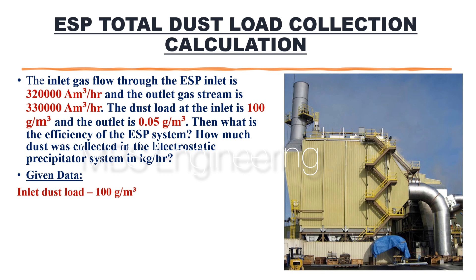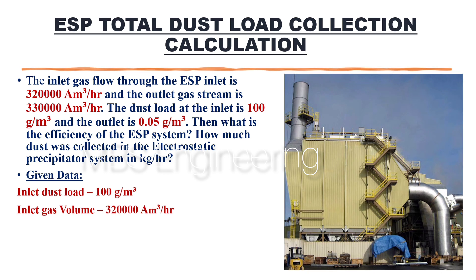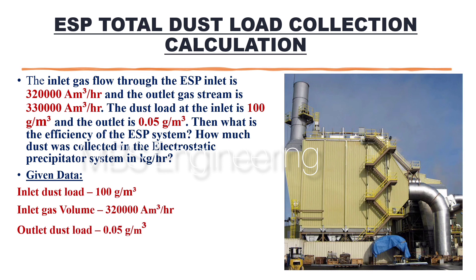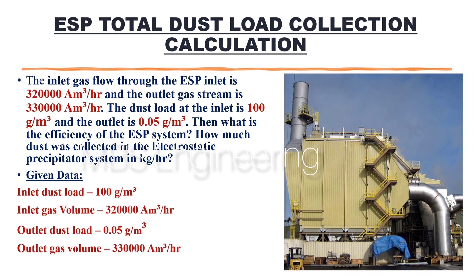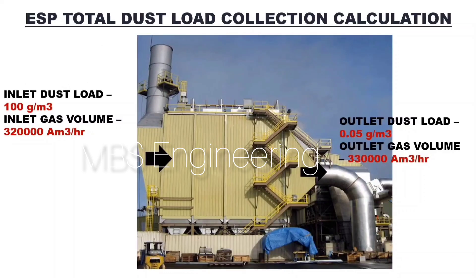Given data: As per the above scenario, the below parameters are given. The inlet dust load concentration is 100 grams per cubic meter. The inlet gas volume is 3,20,000 cubic meters per hour. The outlet dust load concentration is 0.05 grams per cubic meter. The outlet gas volume is 3,30,000 cubic meters per hour. Please refer to the below snaps to understand how to calculate the ESP total dust load collection in the given inlet and outlet dust concentration and gas volume.